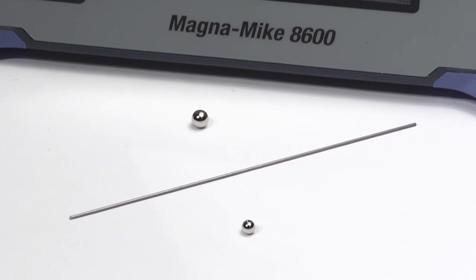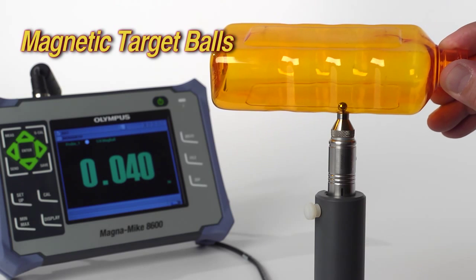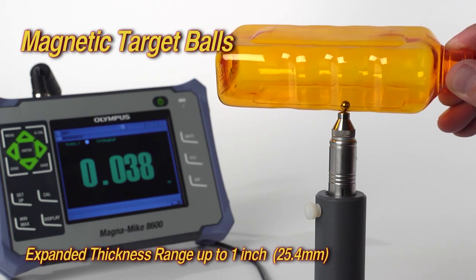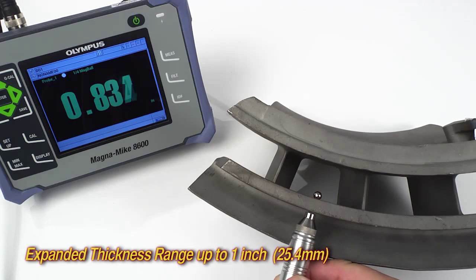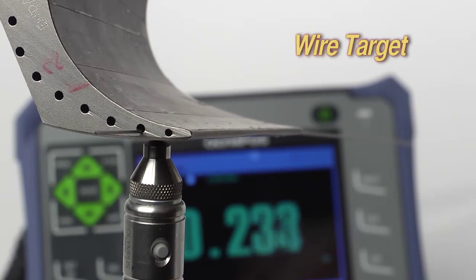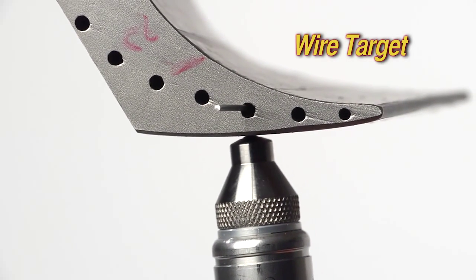The Magna-Mike 8600 can be used with three new targets: two magnetic target balls and a wire target. The magnetic target balls greatly increase the maximum possible thickness range of up to one inch or 25.4 millimeters. This new measurement range is ideally suited for applications such as aerospace castings, which cannot be measured accurately using ultrasonic instruments due to varying grain structure and sound velocity. The wire target can be used to measure wall thickness in applications such as gun drilled holes and turbine blade cooling holes.